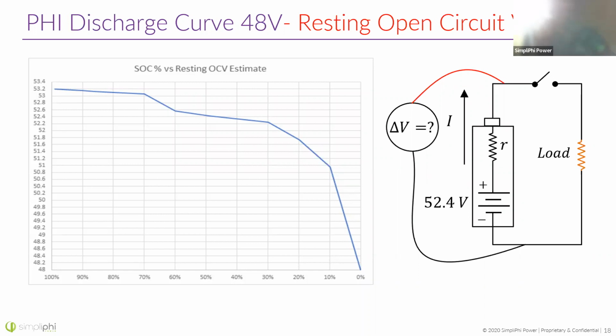But here's what the discharging cycle looks like. As the battery is discharging, you see that the voltage remains fairly constant compared to lead acid batteries. Lead acid batteries and AGM batteries have a much steeper curve here. One of the advantages of lithium batteries is that the curve is relatively flat. One of the disadvantages is that, because the curve is relatively flat, small changes in voltage can mean a big difference in state of charge. So as we look at the state of charge, at 100% state of charge we're starting at about 53 volts, right? Still around 53 volts, just a little bit less, we're looking at 70% state of charge, okay? And so it stays relatively flat.